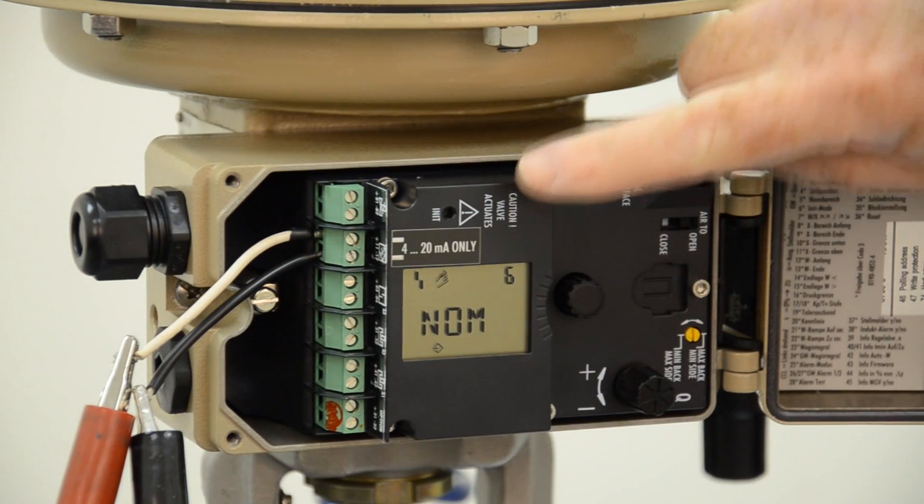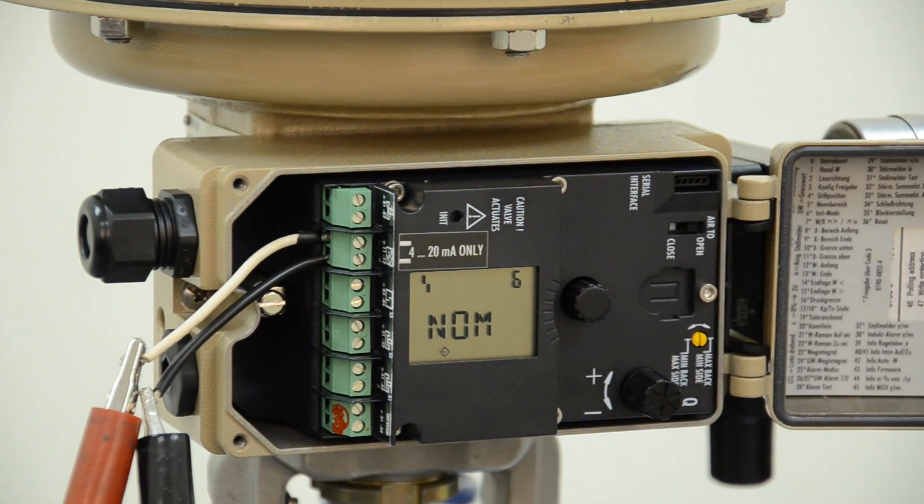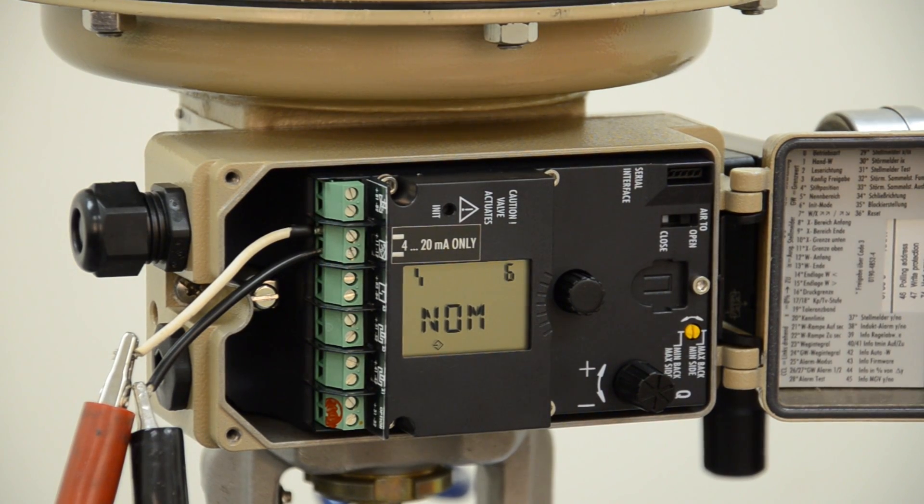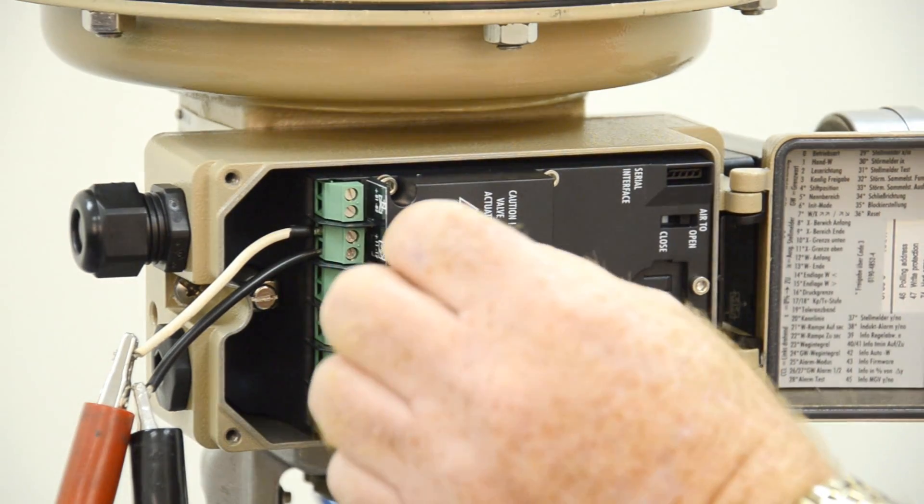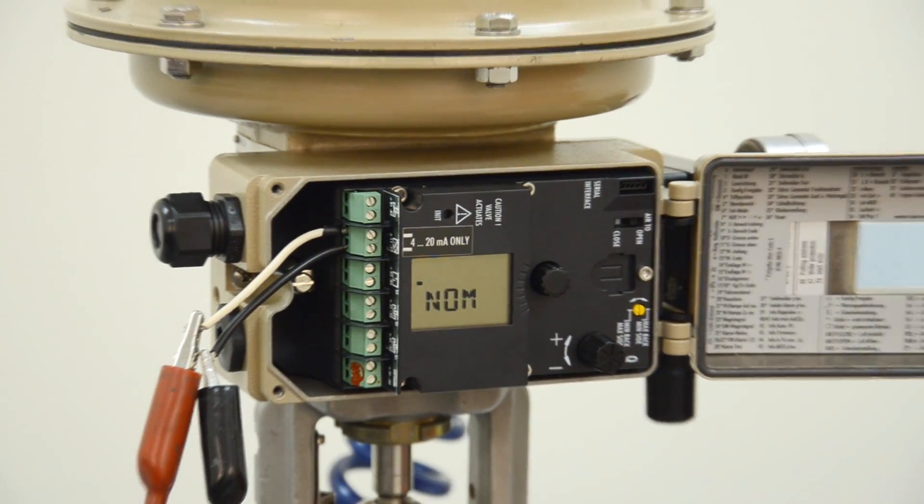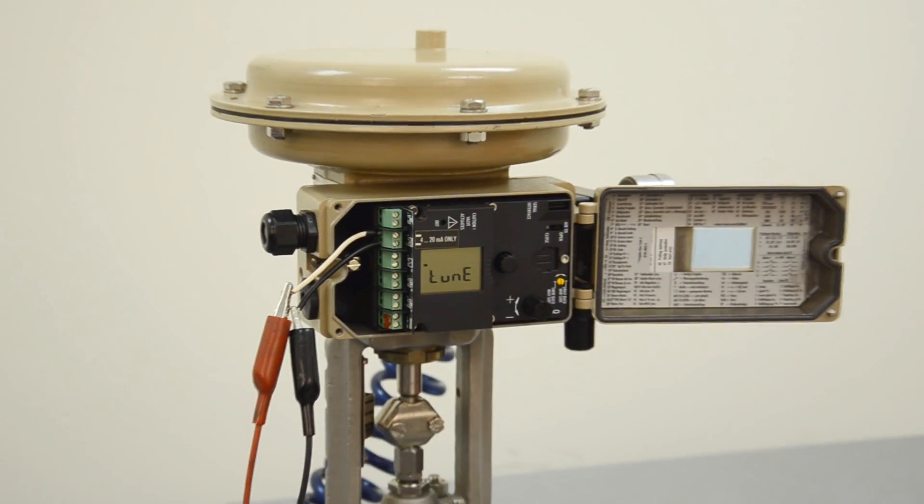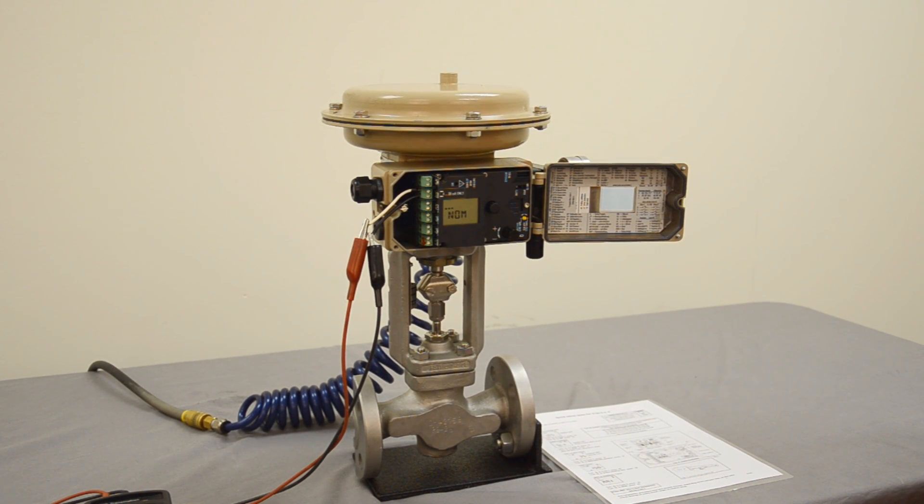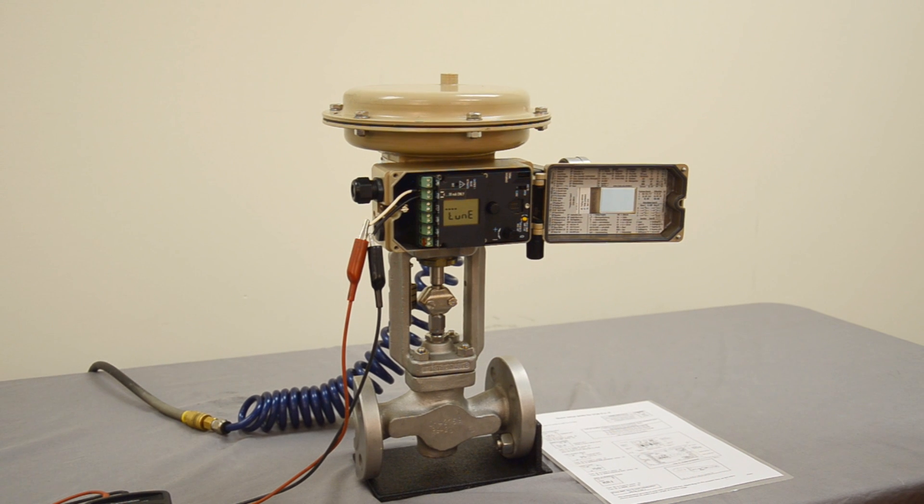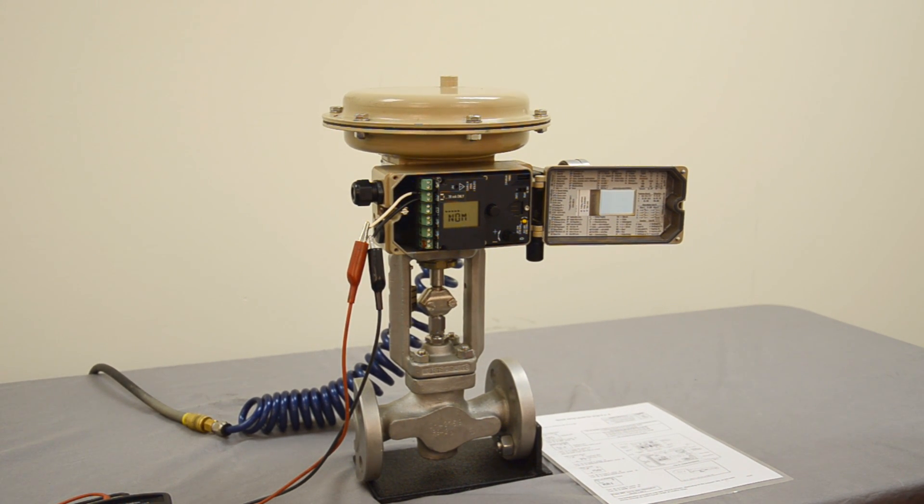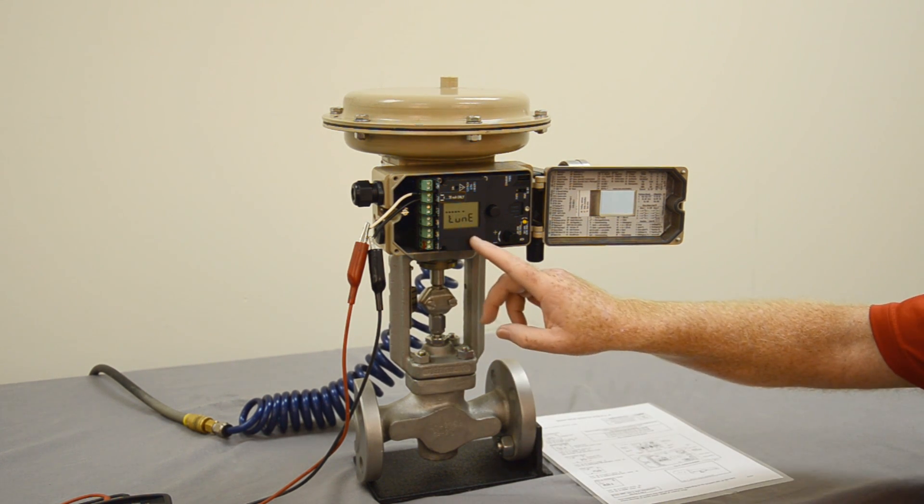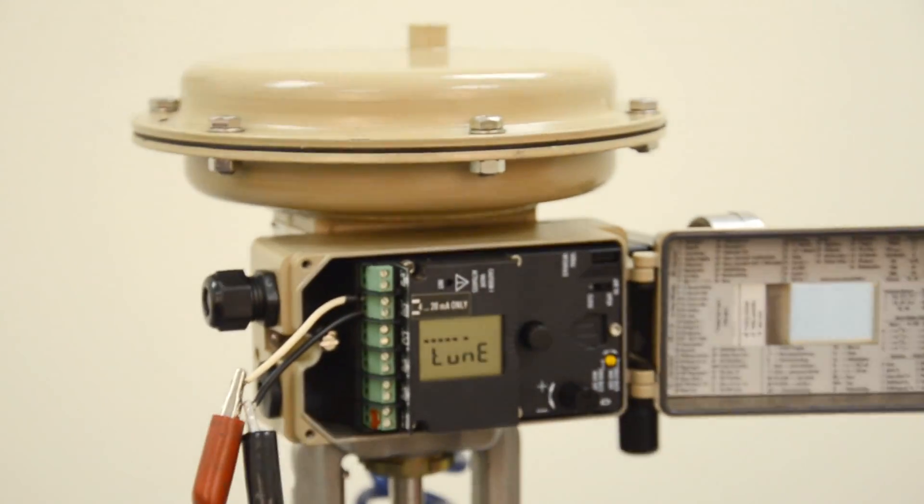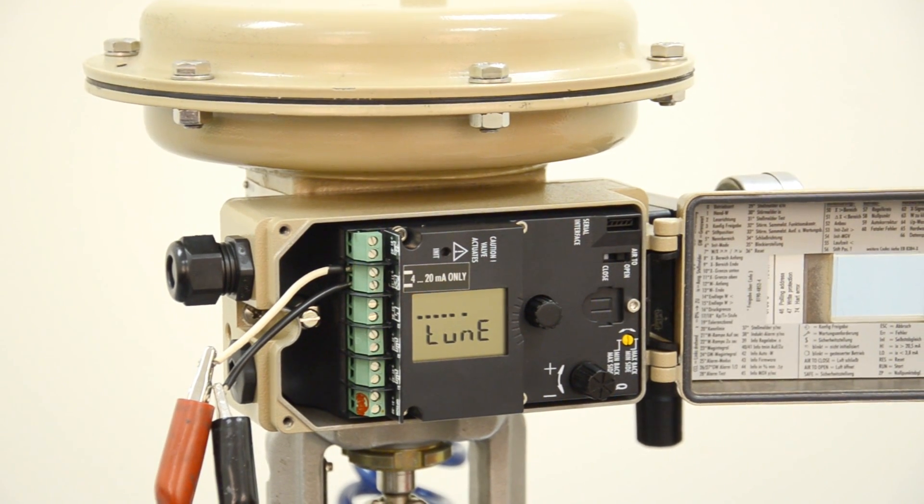There is a button right here, which is our initialization button. You need a small pin or something that can fit into a real small hole, paper clip or something. And you would come in here and press. And the positioner will go through a complete range of the valve, 4 milliamps, 20 milliamps, and different pressure ranges to calibrate. As it's calibrating, there's a bar located on the display that shows you your progress. And this will take a couple minutes to go through the whole process.